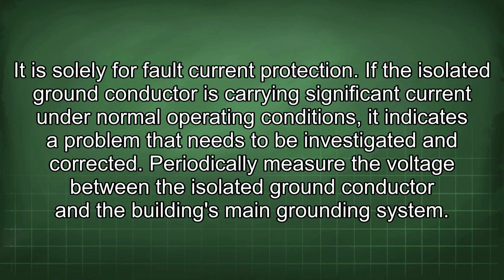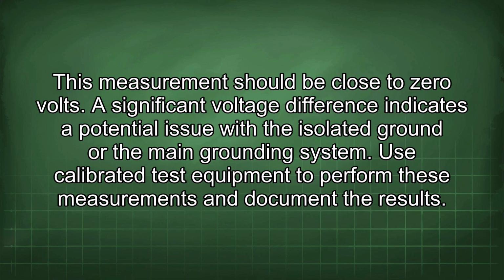Periodically measure the voltage between the isolated ground conductor and the building's main grounding system. This measurement should be close to 0 volts. A significant voltage difference indicates a potential issue with the isolated ground or the main grounding system. Use calibrated test equipment to perform these measurements and document the results.